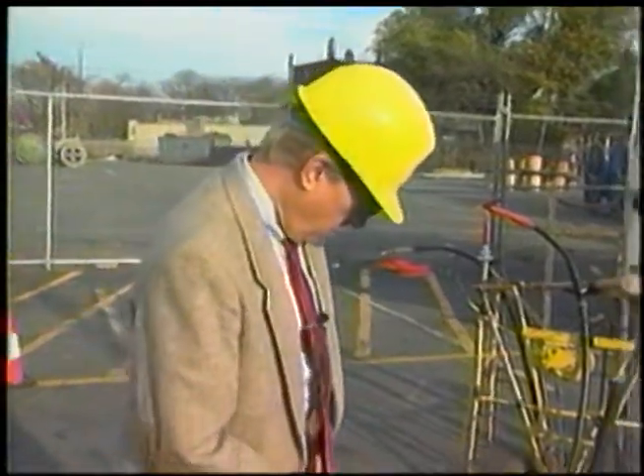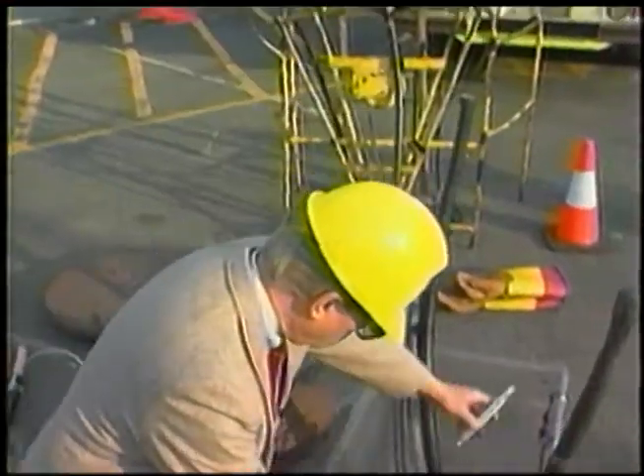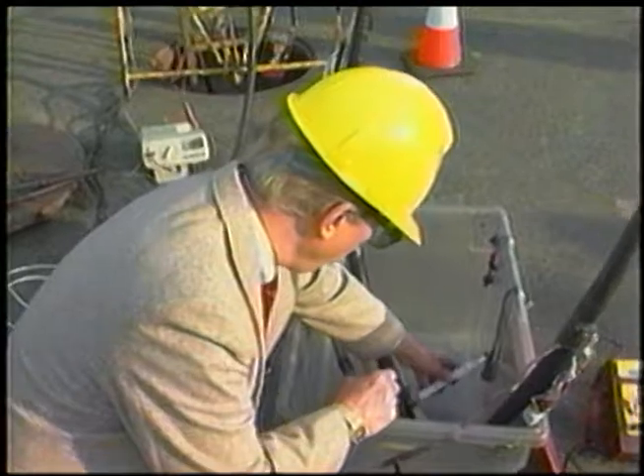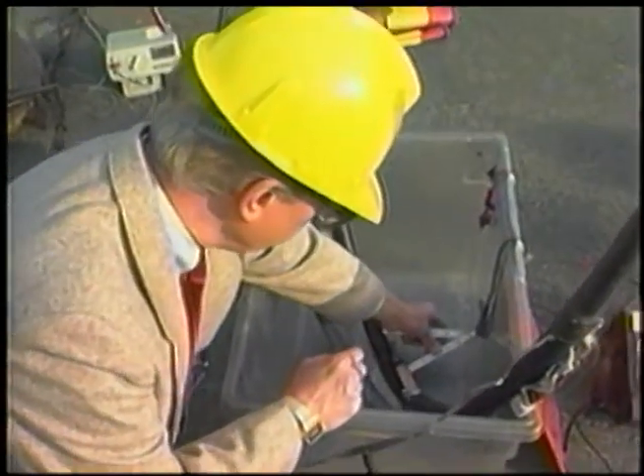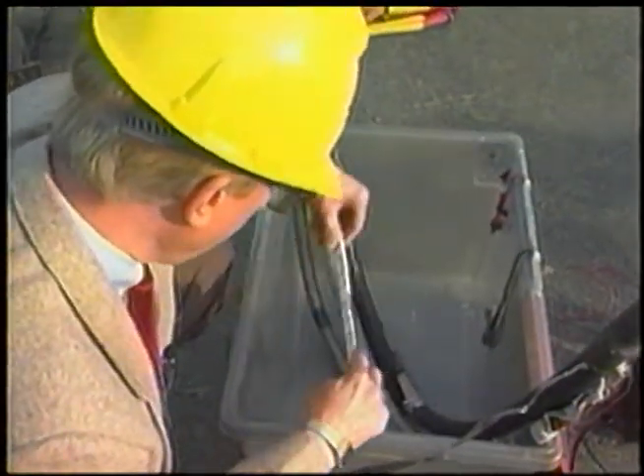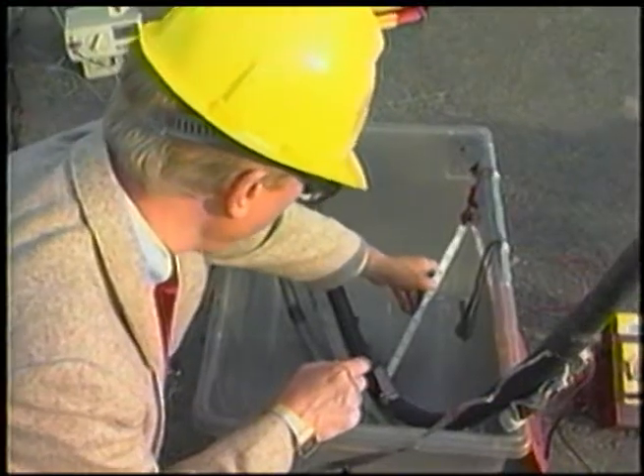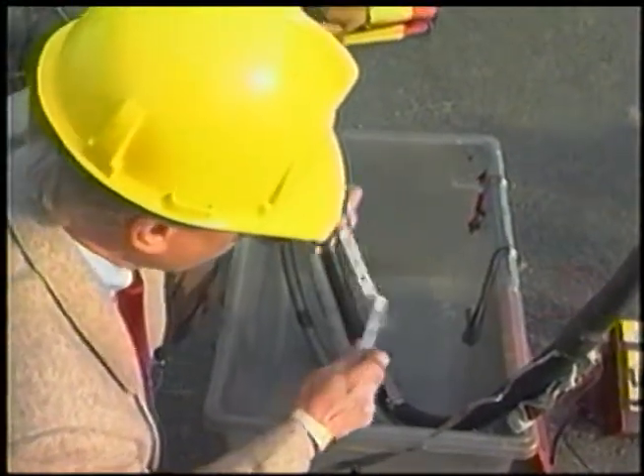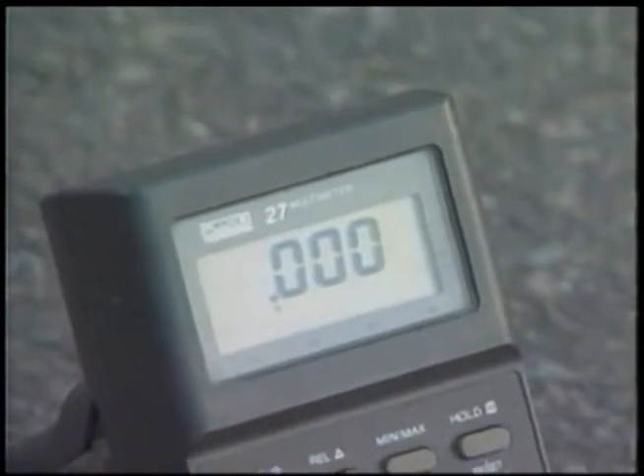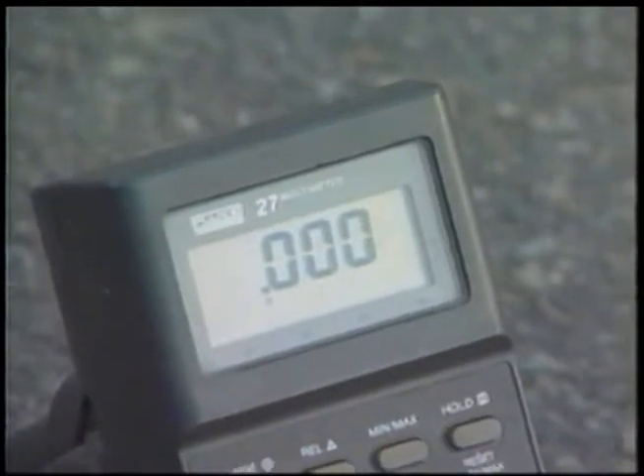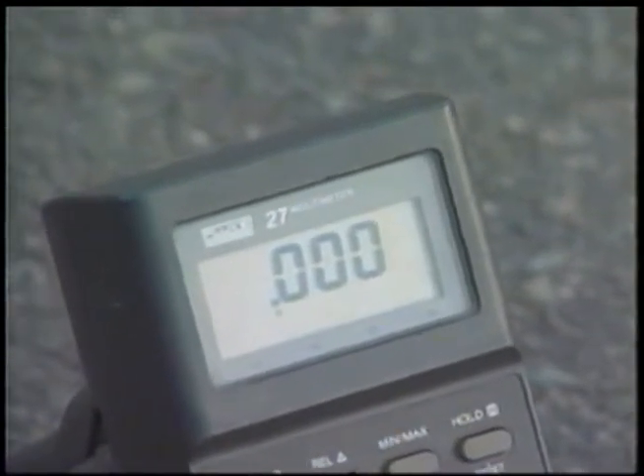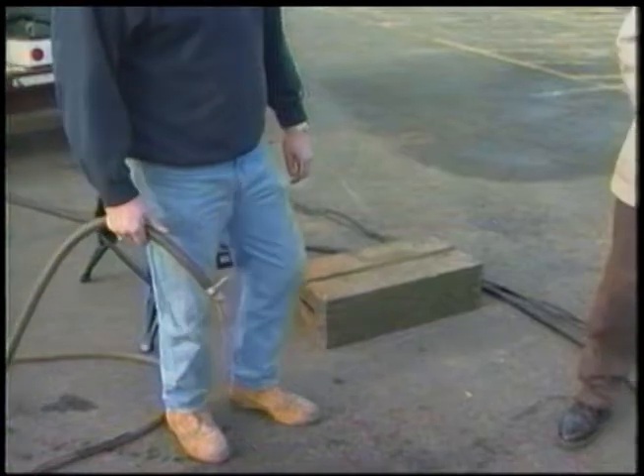Now we're going to fill up the bucket with water, and we're going to measure the voltage that's inside the water. What we have here, we put in two probes. The first probe, the black probe, is set 6 inches away from the fault. The red probe is set 12 inches away from the fault. And what we're going to do, with this meter, is measure the voltage in the water between the water and ground. Okay, Dennis, let's fill up the bucket with water.